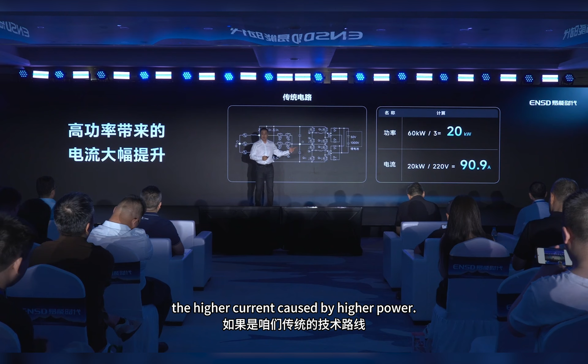What is the second major design challenge? The second big challenge actually comes from the higher current caused by higher power. As we all know, when current rises on a traditional technical route, if you build a 60 kilowatt unit, each phase of a 3-phase Vienna carries 20 kilowatts at 220 volts. The theoretical current is 90.9 — that is a huge current. Many of our peers on traditional architectures have tried to engineer around it. They say, we'll bring in 380 volts.